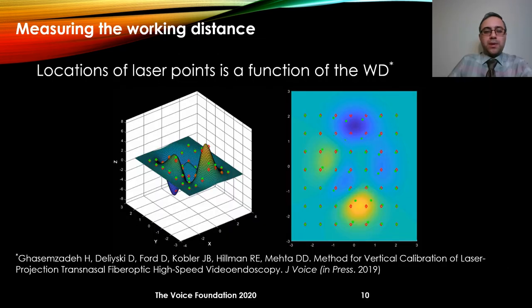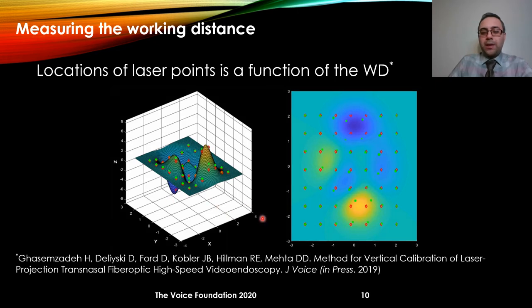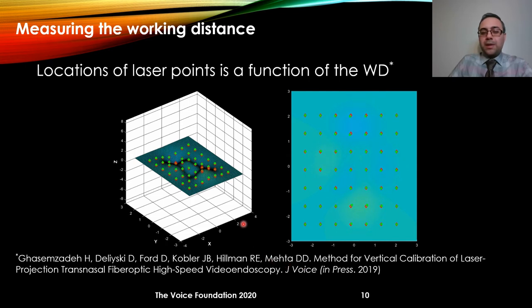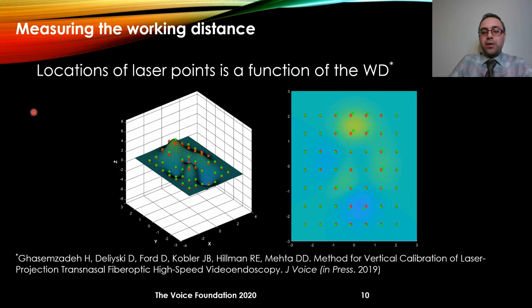In order to do horizontal measurement, we need to determine the distance between the object and the tip of the endoscope. This simulation shows the main principle behind that. There are two sets of points: the red points denote the position of the laser point if the surface were flat, and the green points show the actual position of the laser point as the surface deforms. We can use that information for estimating the distance between each of these points and the endoscope. If you are interested, you can refer to the article already published in the Journal of Voice.